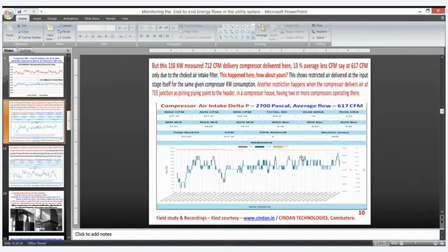This is a case study done by Cindan Technologies, Coimbatore. It is a 110 kilowatt screw compressor, supposed to deliver 712 CFM, the rated CFM, but at 2700 pascals with the choked filter, it could deliver only 617 CFM. The graphs were taken for an hour, for a shift, for a day, and studied for months also. As and when the filter gets choked, the flow rate automatically drops. This is where we have to confirm.